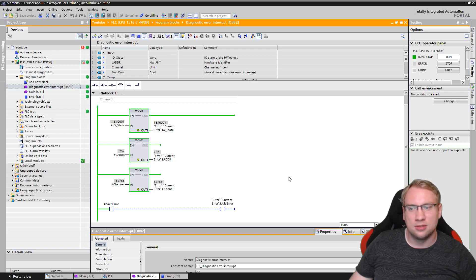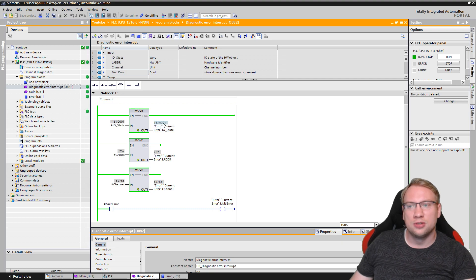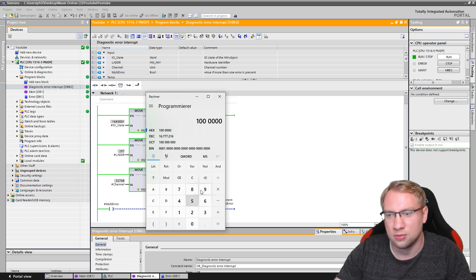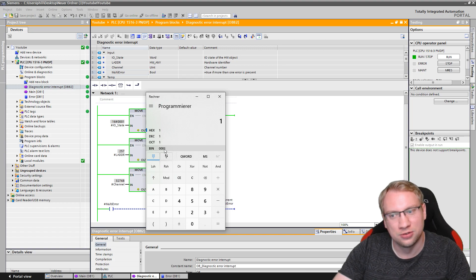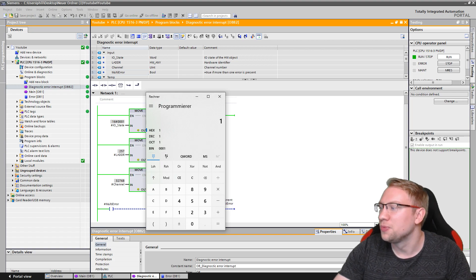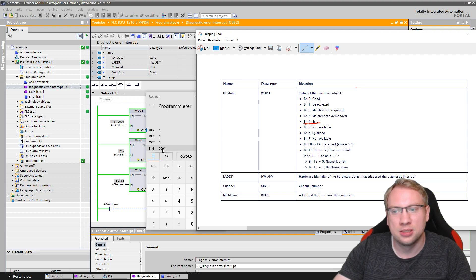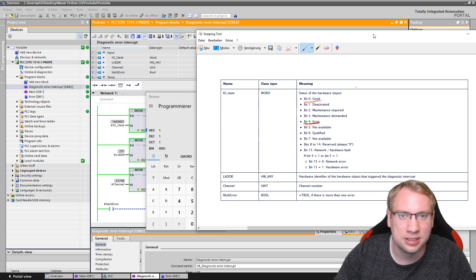Now let's see what I did next. The io_state is 0x0001, which in binary is bit zero active — bit zero means the module is good. Hardware identifier is still 257 — the same module. So we can see the error is gone and everything is fine again.